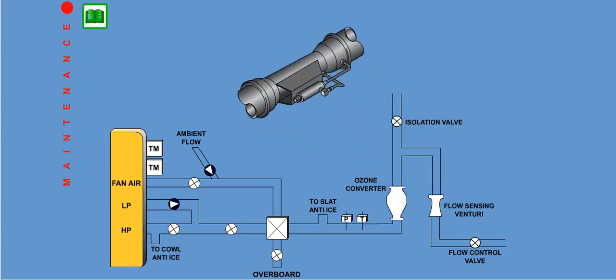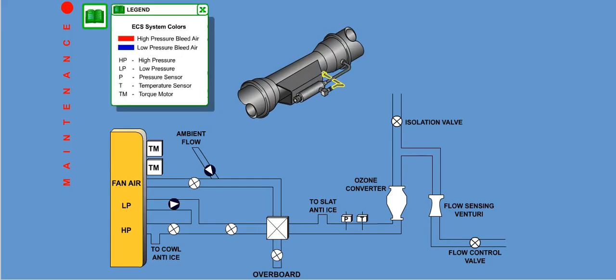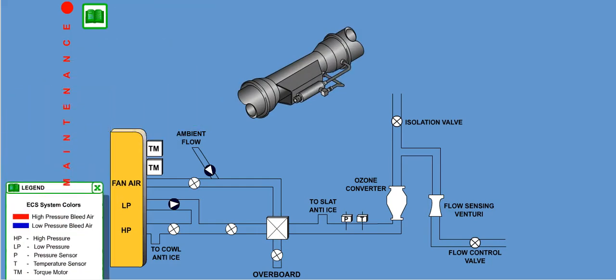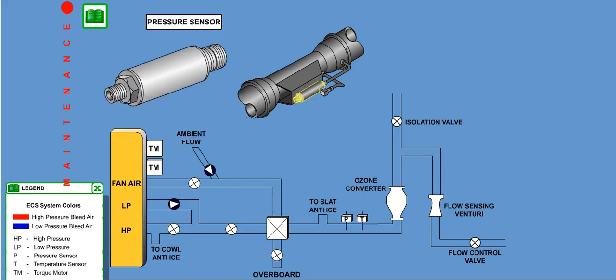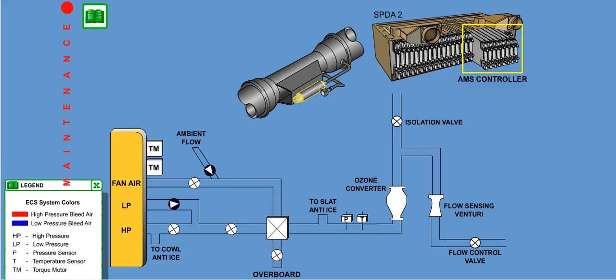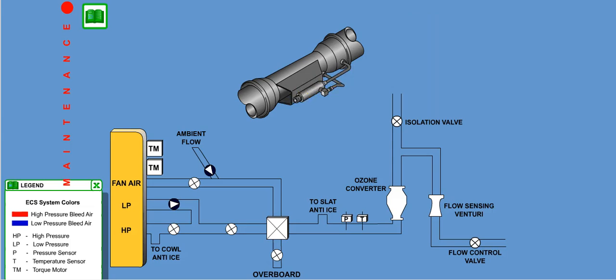The Venturi contains pressure-sensing ports on the upstream and downstream side of the duct orifice. Airflow across this duct is measured by a differential pressure sensor mounted on the Venturi. The sensor provides a 0 to 10 volt DC electronic signal to the AMS controller. The sensor is hermetically sealed and has two input pressure ports, an internal pressure transducer, and an electric connector.